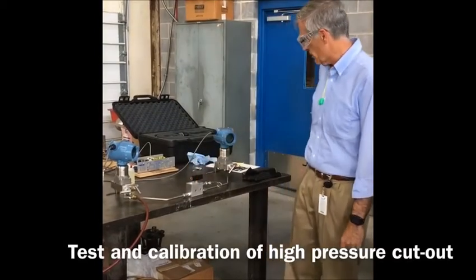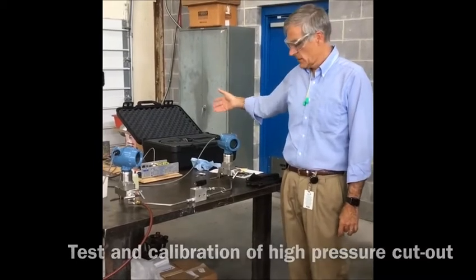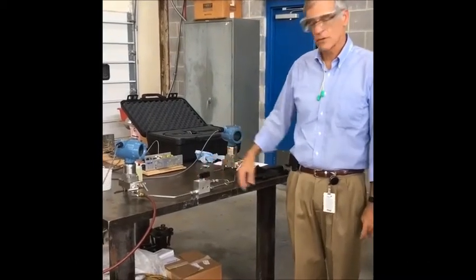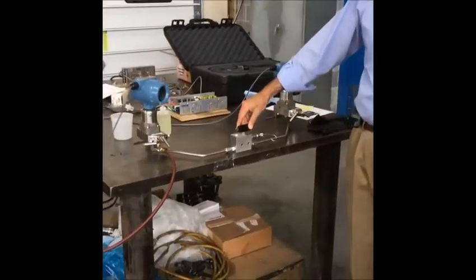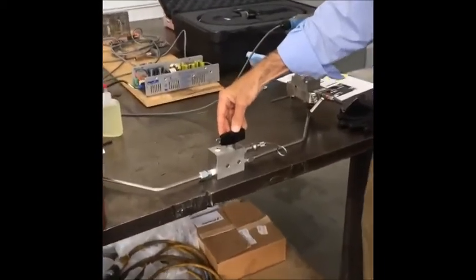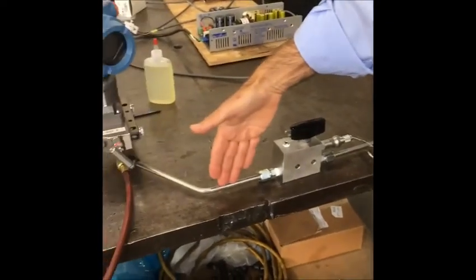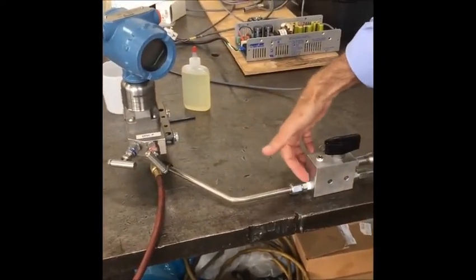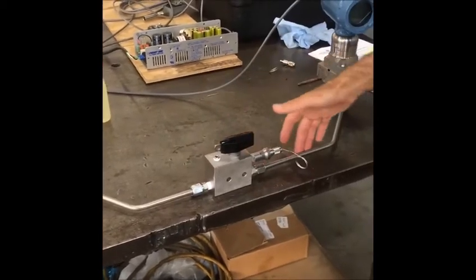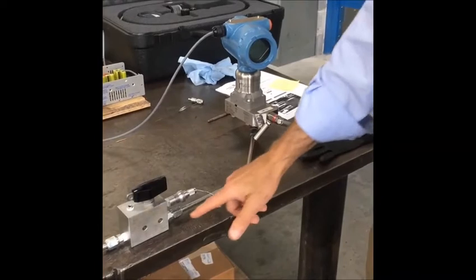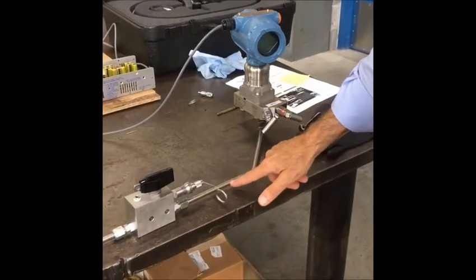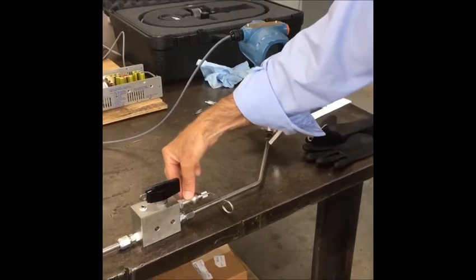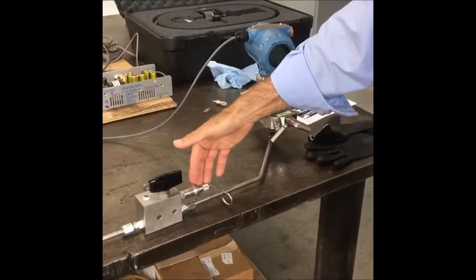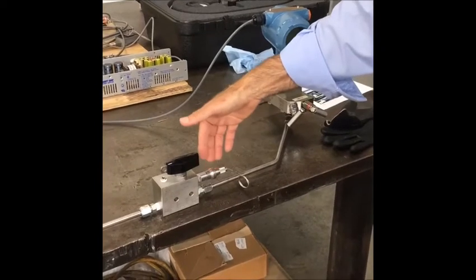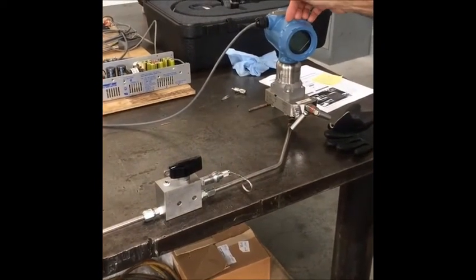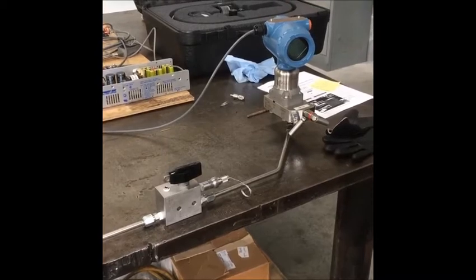Block and our calibration test kit. So first, maybe we can zoom up here on the block. This is the test block that would be installed on a compressor package. We'll have discharge pressure coming in from the compressor into the block, and then the high pressure cutout would be installed on the outlet line from the block. And then we have a test port. On the test port, we will be using our calibration pump in order to test the high pressure cutout using oil pressure. So let's go look at the test pump.